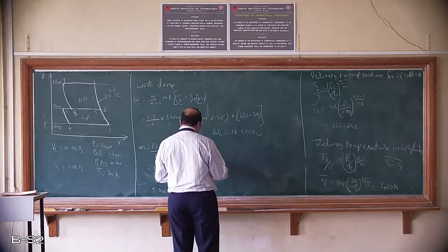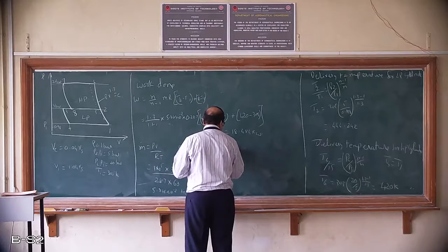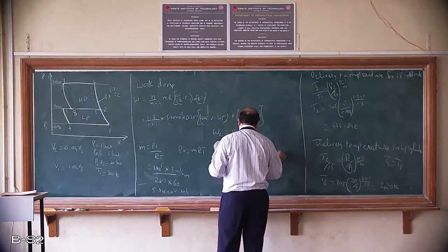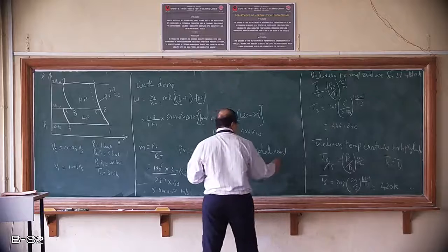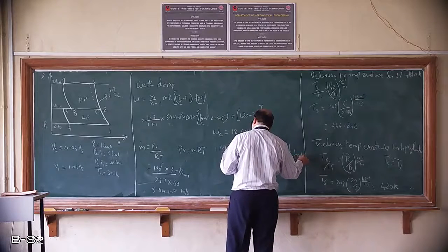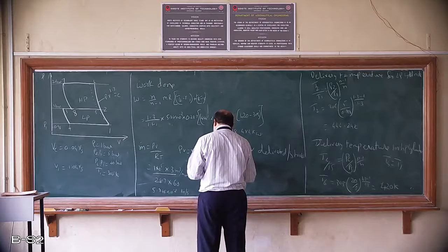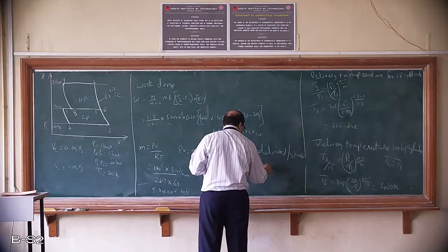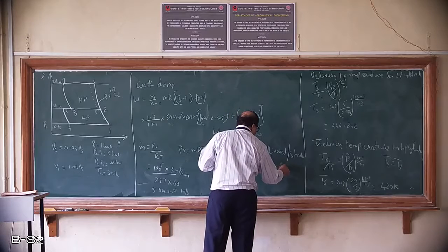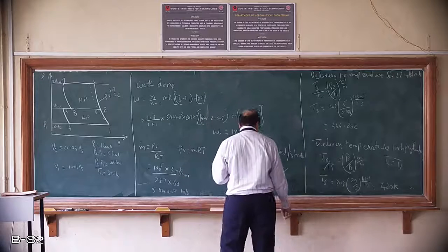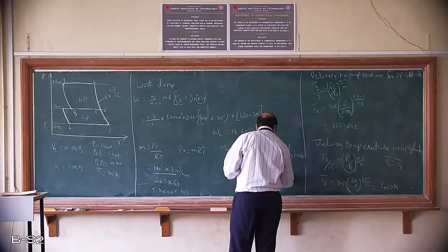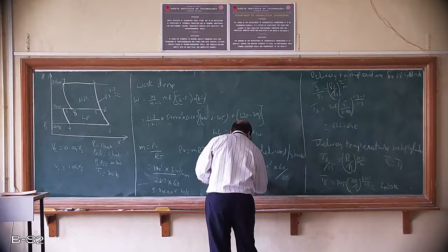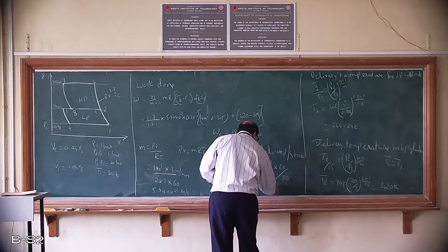So mass of air delivered is what? So mass of air delivered per stroke is, we know mass of air per second we have calculated, 5.846 into 10 to the power of minus 2. So per minute, so we want it per stroke, so 60 divided by 300 RPM, we'll get it for per stroke, so 1.1692 into 10 raised to minus 2 kg.